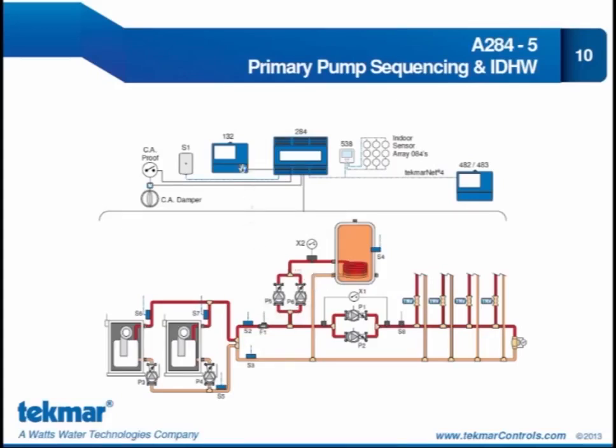We have two domestic hot water pumps that are being controlled in this case by a 132 pump sequencer. So the domestic hot water pump output on the 284 is being used to provide the pump demand on the 132, and the 132 is taking care of that domestic hot water pump sequencing. And of course we would have to prove flow. Here we are proving flow with a flow switch. You can see the space heating zones are equipped with TRVs. So this is a type of application that you might find in a small apartment complex where we have one thermostat located in the boiler room, and we have individual indoor sensors in the units.